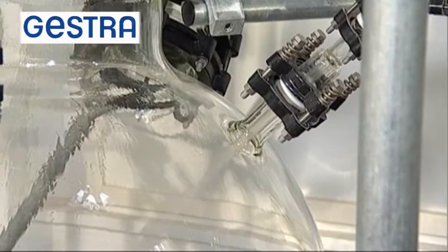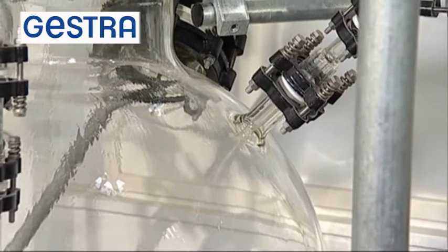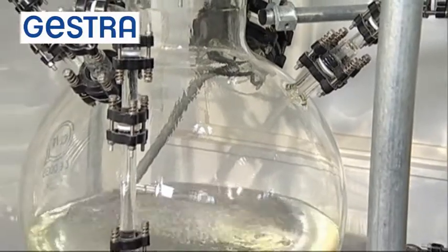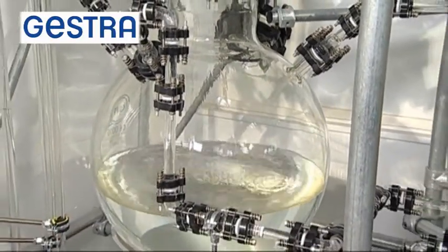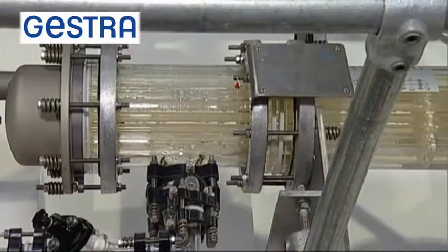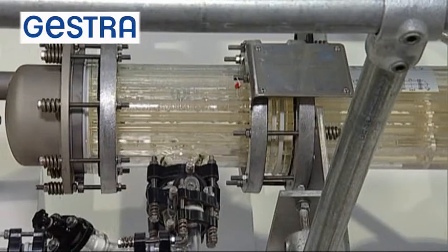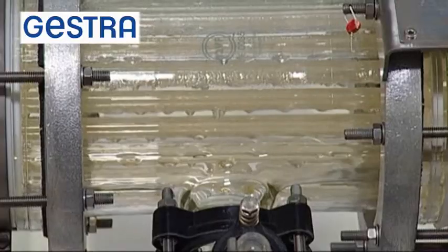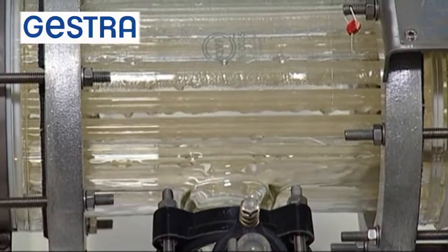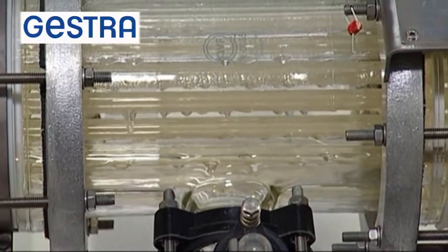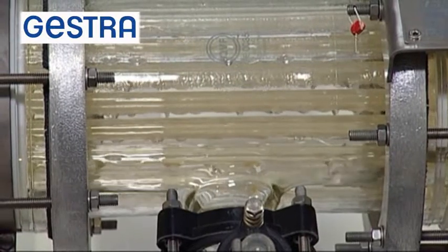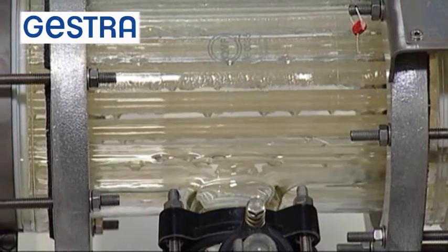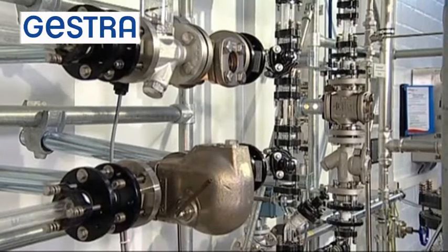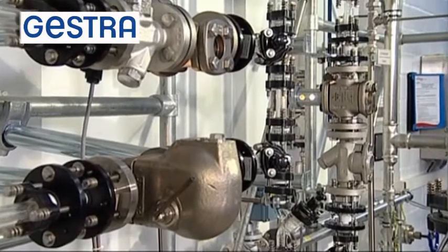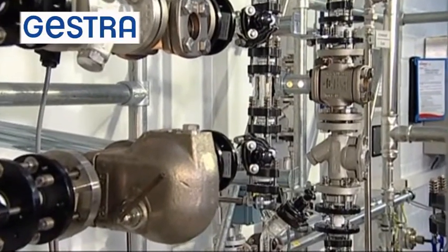After passing through the steam traps, the condensate is collected in a glass condensate tank at normal atmospheric pressure. By looking into the heat exchanger, we can see the condensation on the individual glass tubes through which the cooling water flows from right to left. The drops that form soon fall off the tubes, collect at the bottom of the heat exchanger, and flow towards the outlet. The steam traps used for draining the heat exchanger are mounted below the heat exchanger.